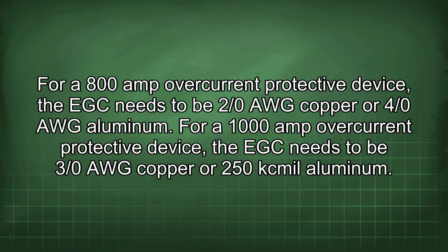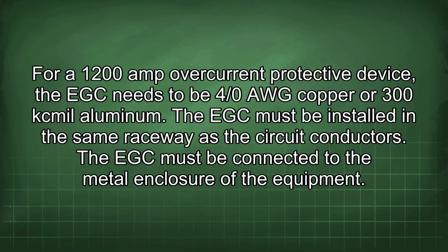For a 1000 amp overcurrent protective device, the EGC needs to be 3/0 AWG copper or 250 kcmil aluminum. For a 1200 amp overcurrent protective device, the EGC needs to be 4/0 AWG copper or 300 kcmil aluminum.